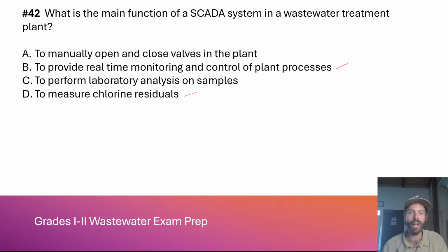There's programmable logic. Now, it will display your chlorine residual measurement, but the actual controller and the sensor actually measure the chlorine residual. SCADA collects the data and projects it to you, the operator, through what is called, and you should know this, HMI, the Human Machine Interface. So we use SCADA pretty generally, like I'm going to check SCADA, and when I say I'm checking SCADA or doing SCADA checks, I'm actually looking at the HMI.